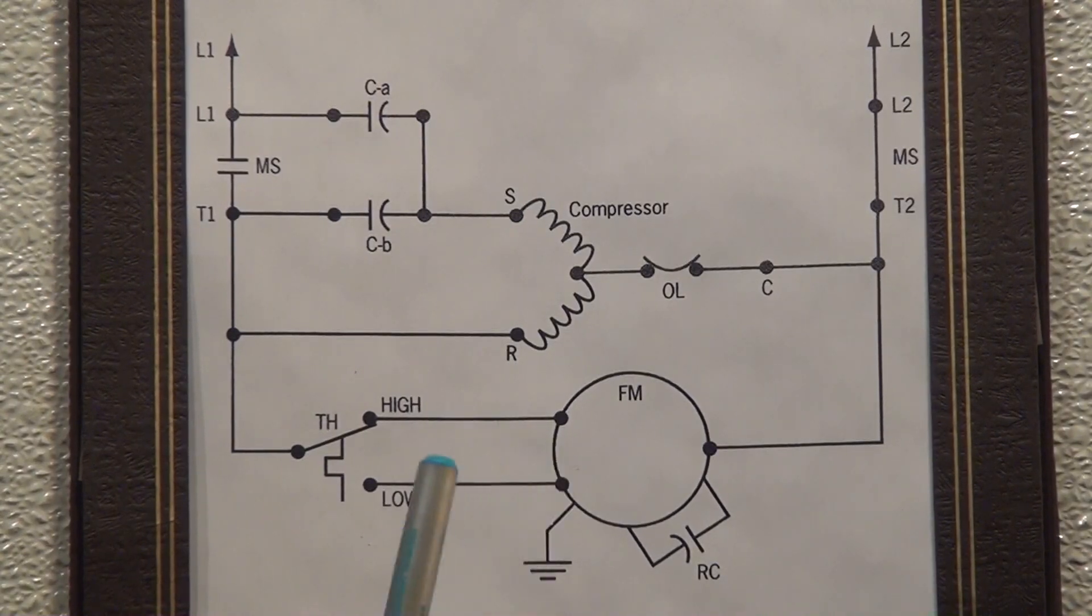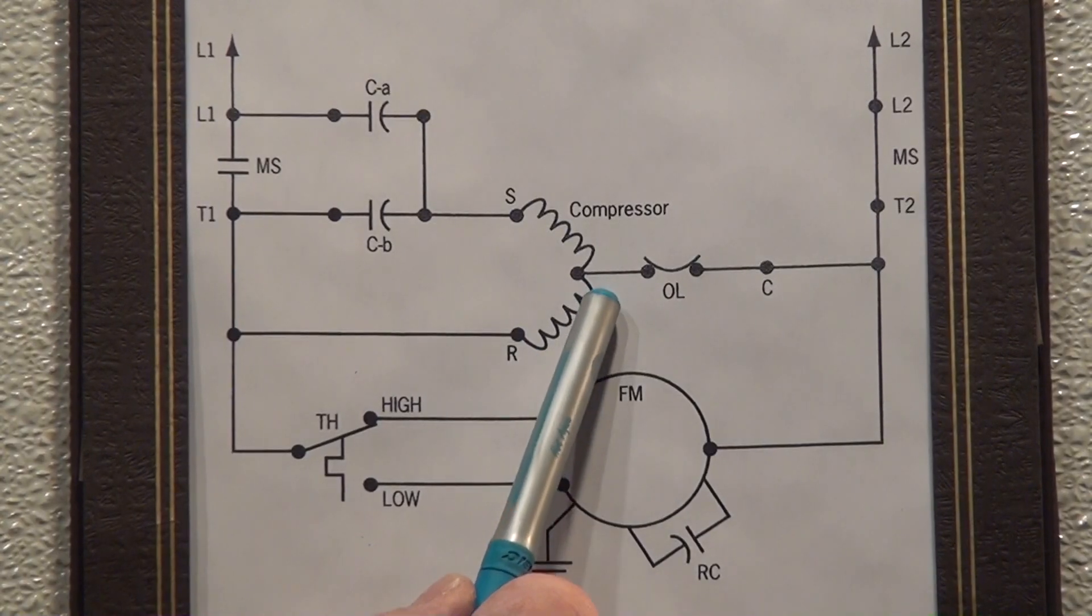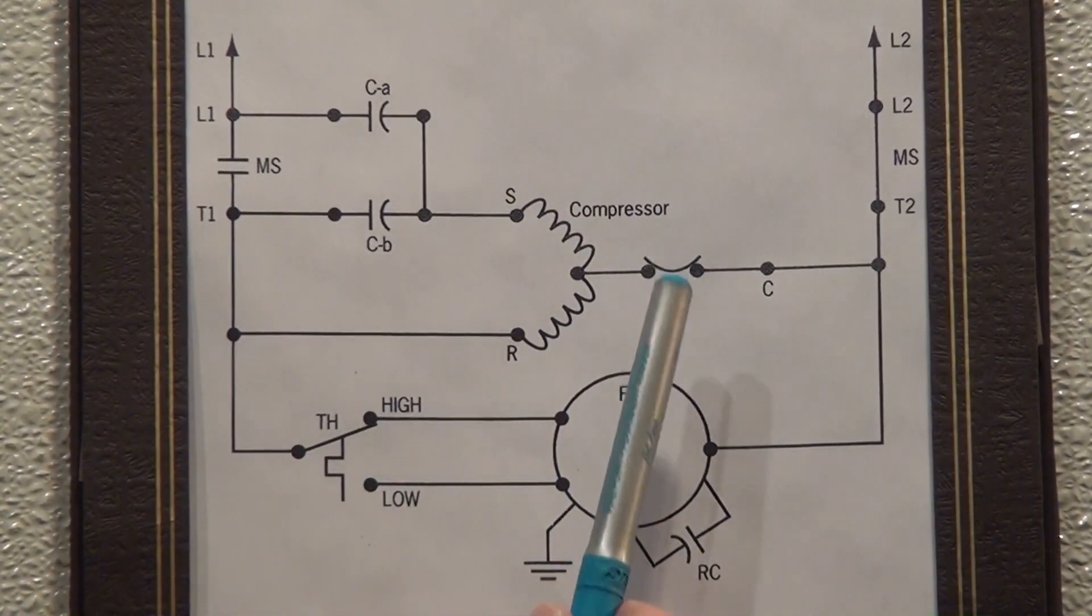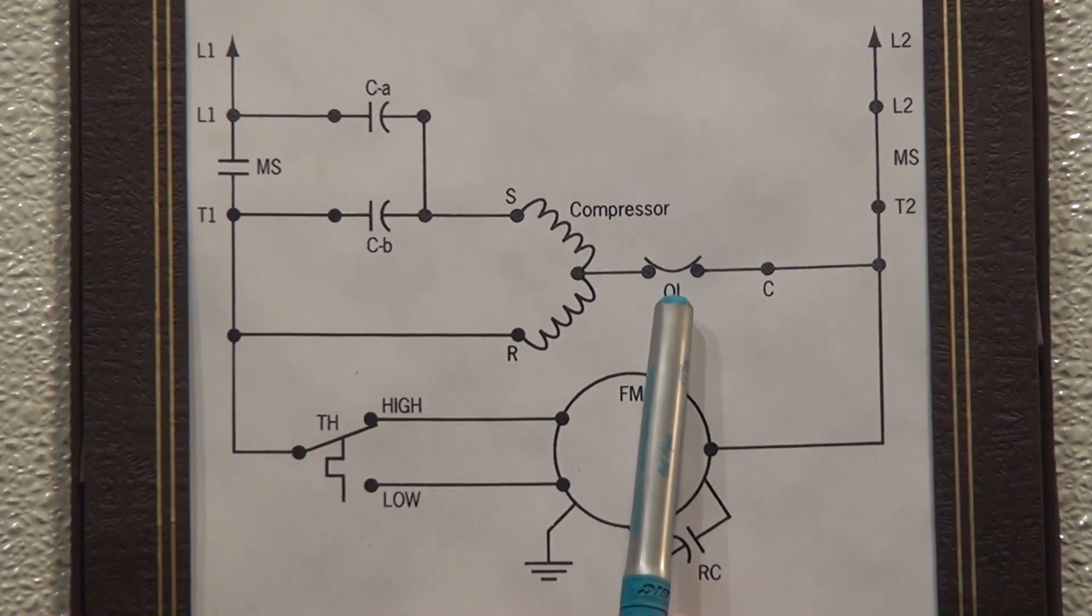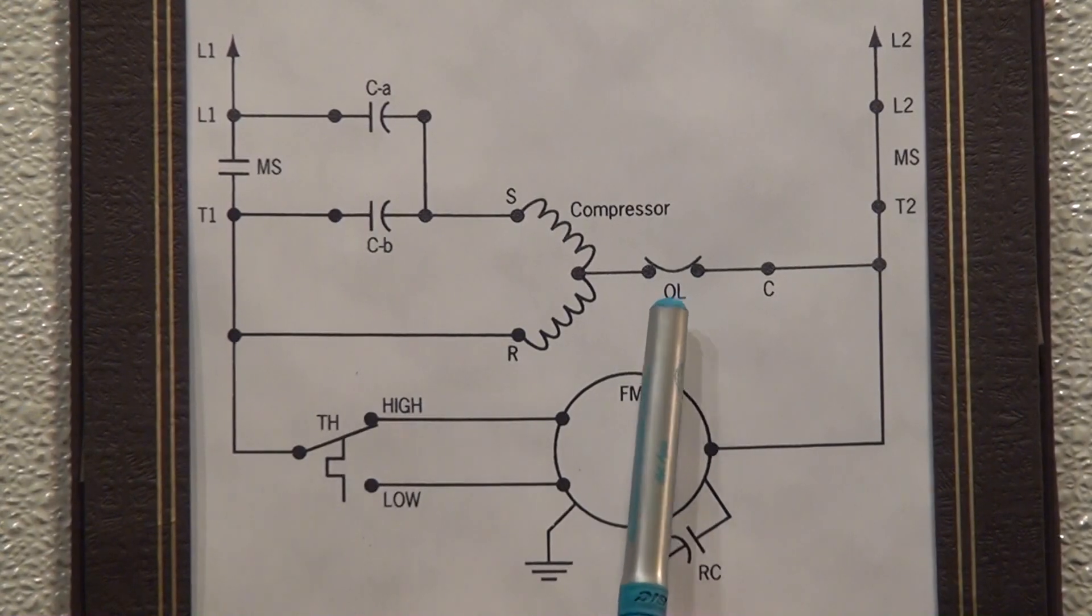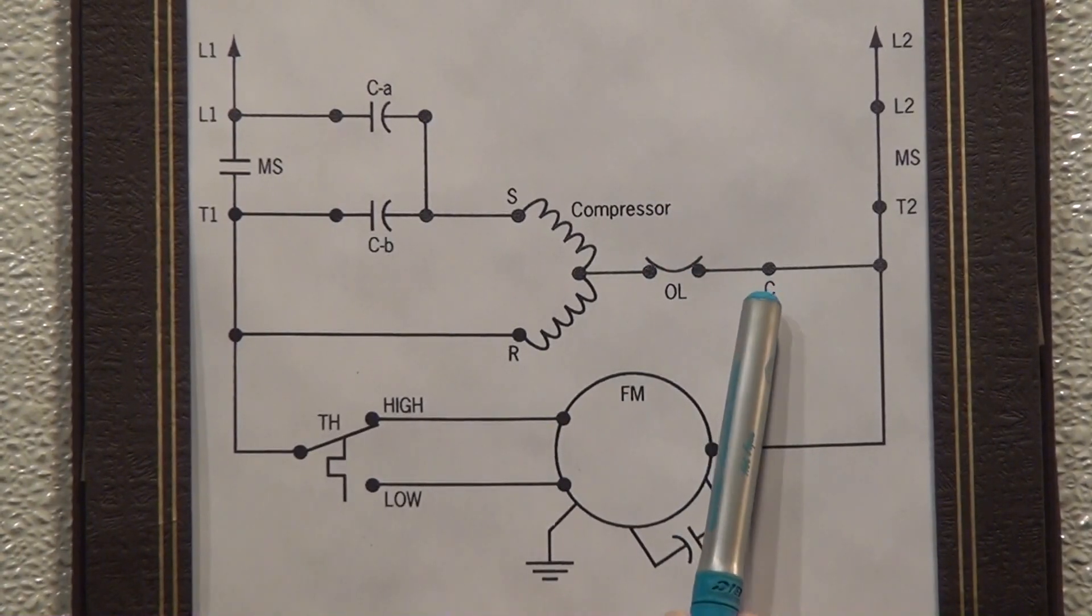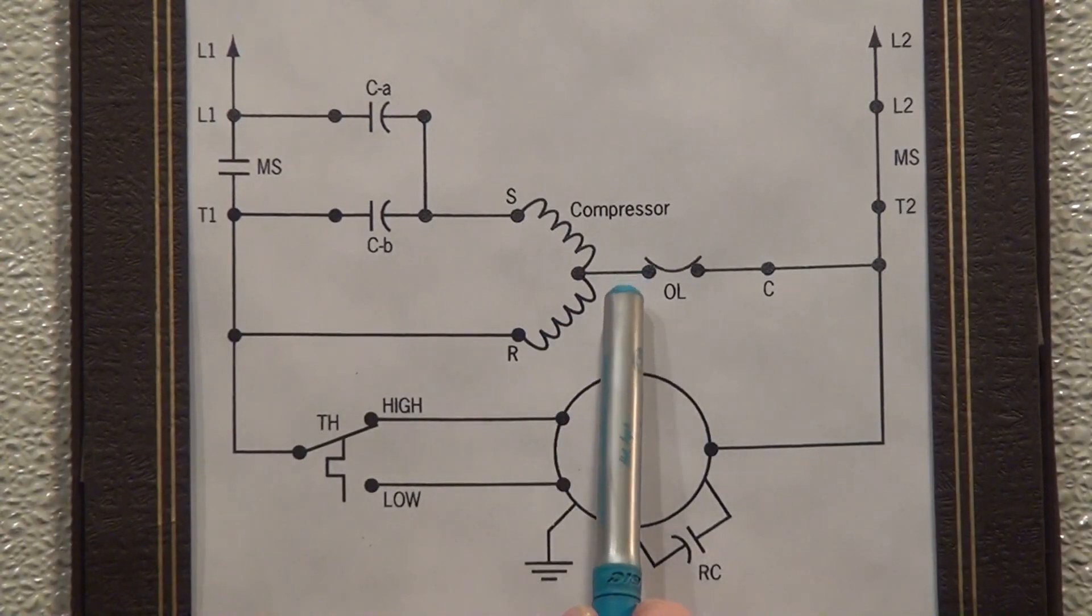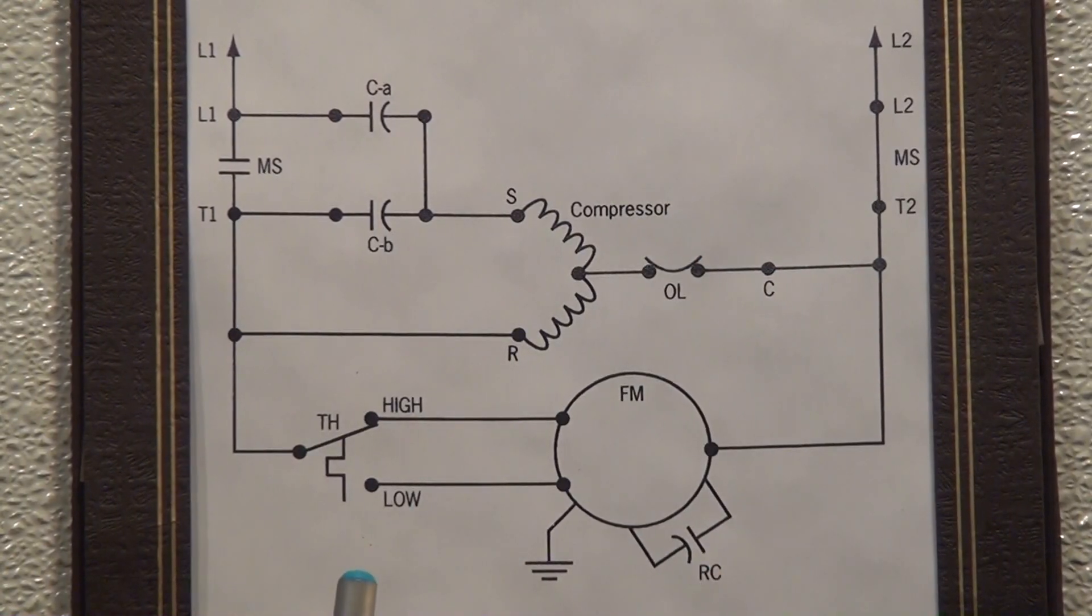Now the compressor itself, as long as we identify the compressor, we can understand the start winding here, the run winding here, and we also have another piece of information about the compressor that we can understand. This compressor has an internal overload protector, and the reason that we know that's true is because OL in this situation is the overload and you're going to notice that it's wired on this side of the common terminal for the compressor. So common, run, and start on the compressor showing the motor windings, and this is showing the internal overload because it's on this side of the common terminal.